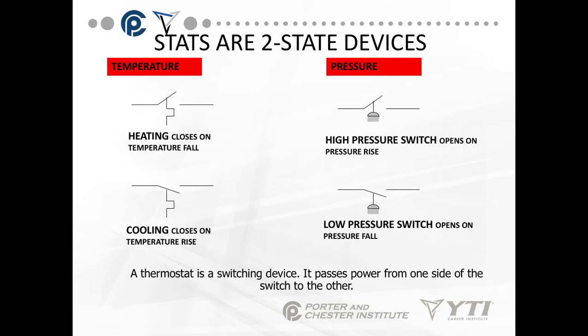Thermostats are two-state devices — they're either on or off. Looking at the schematic symbols of our devices, specifically for cooling, you'll notice it will close on temperature rise. For pressure switches: the low pressure switch opens on pressure fall; the high pressure switch opens on pressure rise and closes on pressure fall. The two bottom ones are the ones you'll see used in refrigeration systems for temperature control.